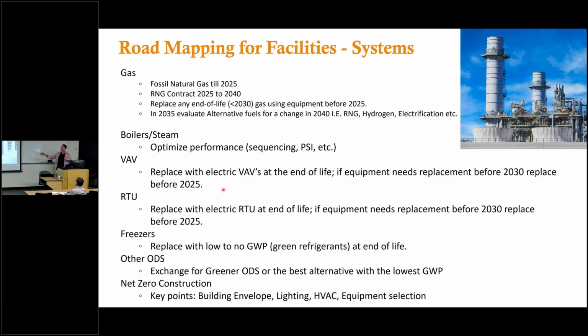Variable airflow - a lot of office spaces have VAV boxes talking to the building management system, opening and closing based on use. There's a lot of smart building technology, and some of it's really cool - like if there are 20 people in a conference room, the system increases airflow, but if nobody's in the space except for one morning, the airflow can be significantly decreased the other days. If you understand carbon dioxide levels, with occupancy sensors or other mechanisms, you can know what the airflow needs to be. There are so many opportunities in building systems - it just needs to be justified with cost to see what makes the most sense for you.